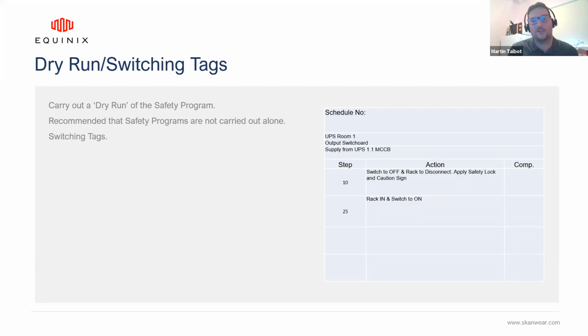And that's applied to the switch, so that when you go and operate it as part of your safety program, you can check on the safety program. Step 10 at UPS room 1, output switchboard, supply from UPS 1.1 MCCB. I'm going to switch this off. My accompanying safety person agrees. The switching program and the switching tag on the switch align. We know we've got the right switch, and we're eliminating human error and opportunities for mistakes.